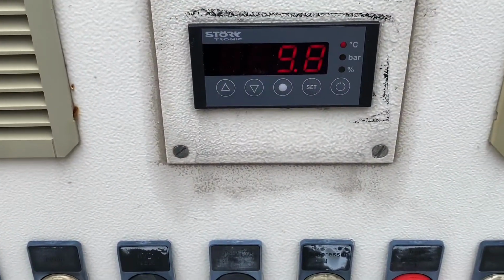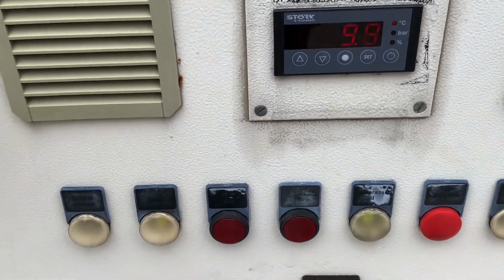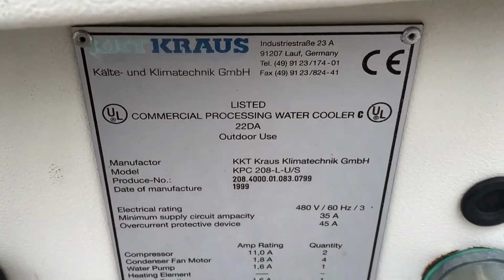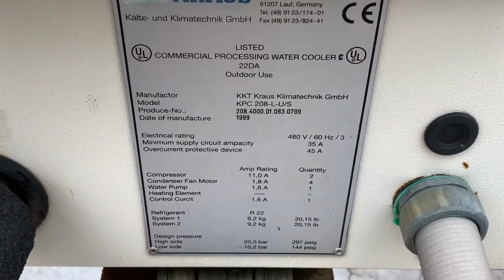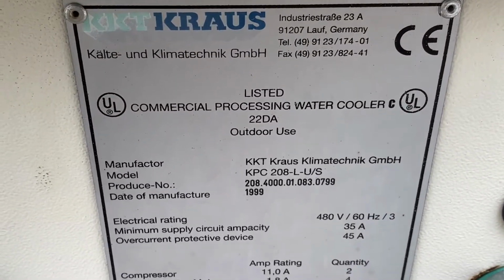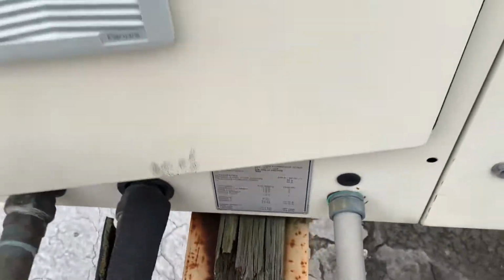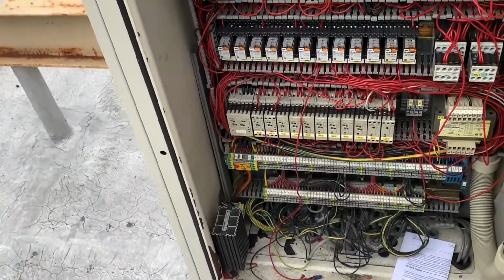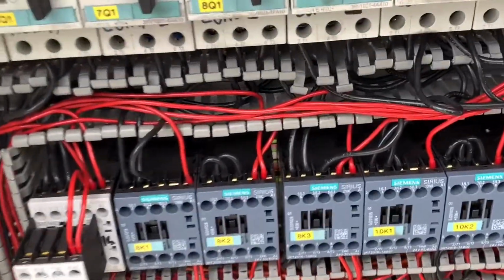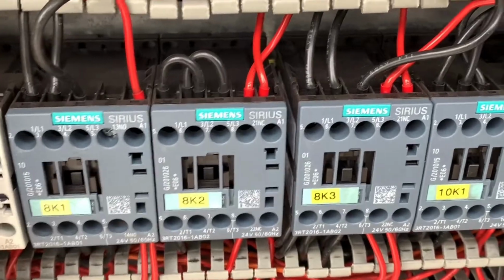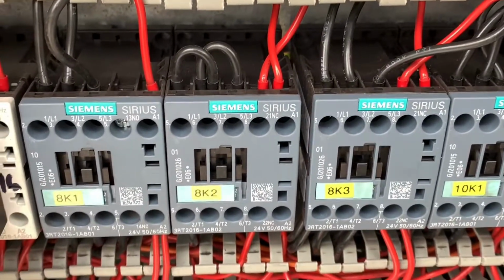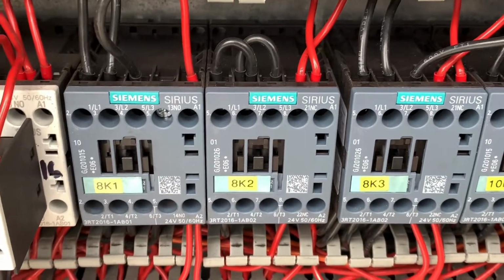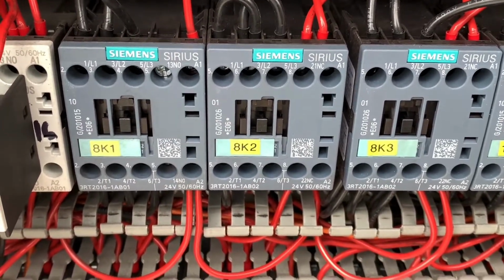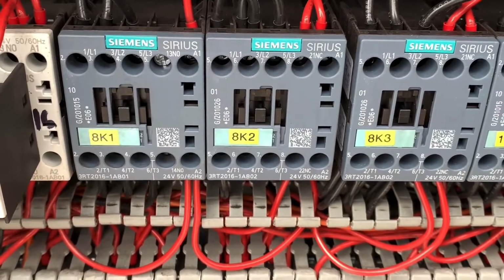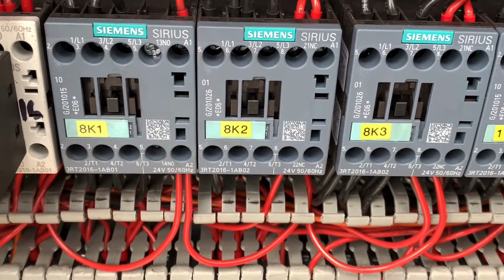So yeah, this is an old KKT chiller, 2008 model, but it's still going. Now, if you have a KKT chiller, and if everything is in tune and is working good, this is how it's supposed to sound. The compressor never turns off. It's extremely unlikely the compressor will cycle off even under low load, because right now it's under low load condition, and you see how it's operating.